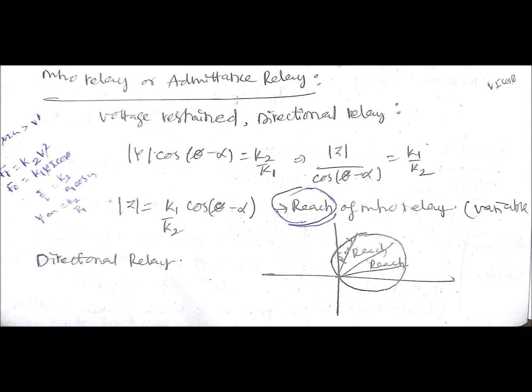The reach of the mho relay varies — if you observe the characteristics, the reach values from the origin of the coordinate system vary for different values of α. Unlike the reactance relay where α is fixed at 90°, here α is not fixed, making reach a variable quantity. However, the characteristics lie completely towards the positive values, which is why the mho relay is a directional relay.